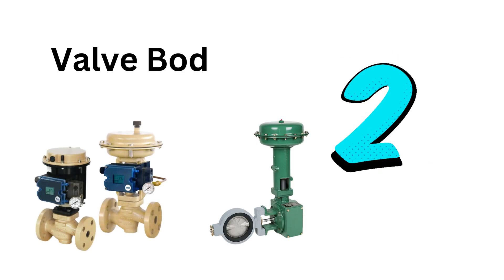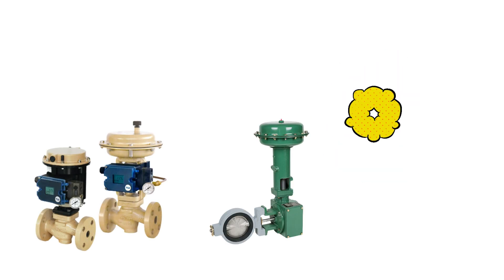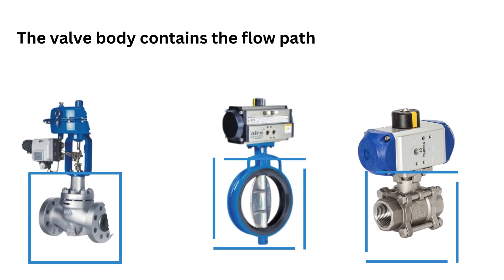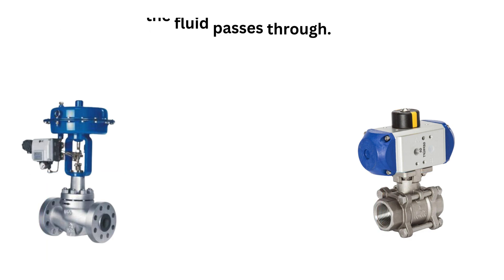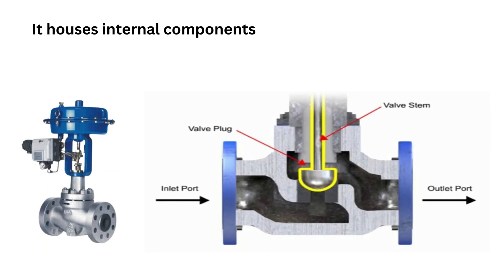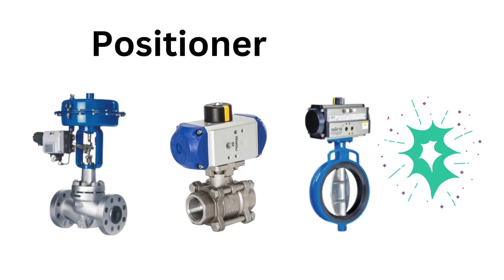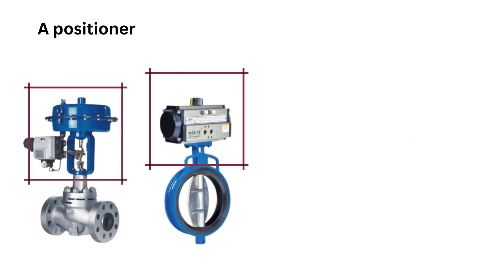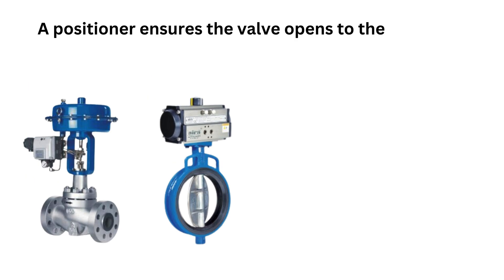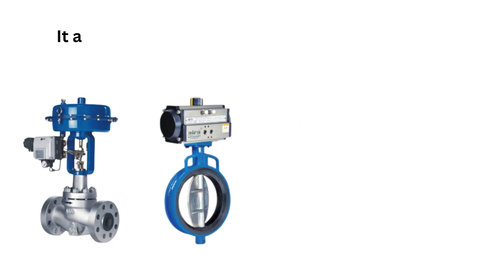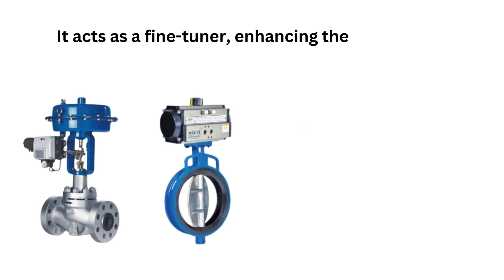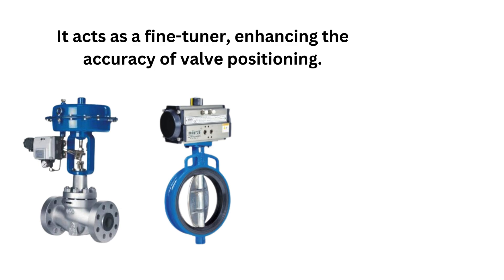The second component is the valve body. The valve body contains the flow path and is where the fluid passes through. It houses internal components like the plug, seat, and stem. The third component is the positioner. A positioner ensures the valve opens to the correct degree based on the control signal. It acts as a fine tuner, enhancing the accuracy of valve positioning.